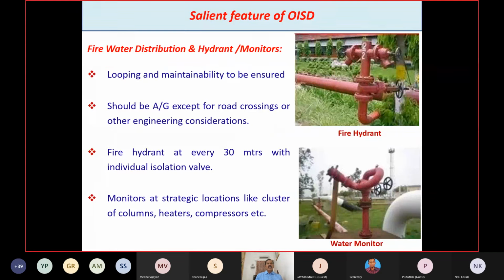Fire water distribution and hydrant monitors, looping and maintainability to be ensured. A closed loop system should be followed to ensure multi-directional flow and uniform pressure in the hydrant network. It should be above ground except for road crossings or other engineering considerations, with a fire hydrant every 30 meters with individual isolation valve, and monitors at strategic locations like clusters of columns, heaters, and compressors. Both hydrants and monitors should be located 15 meters away from any facility.